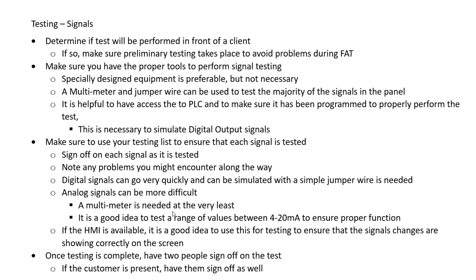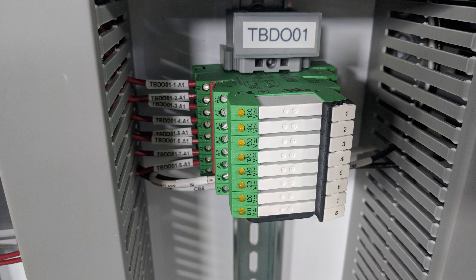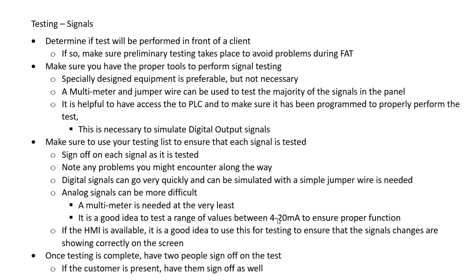Because we also have output signals to measure, this is where we'll need access to the PLC. We'll want to connect to it and measure digital output signals as well as analog output signals. With the analog output signal, you'll need a multimeter as well. With digital output signals, if you're using interposing relays as we do on our panels, you can simply listen for that audible click in the relay to confirm that you're sending that output signal.